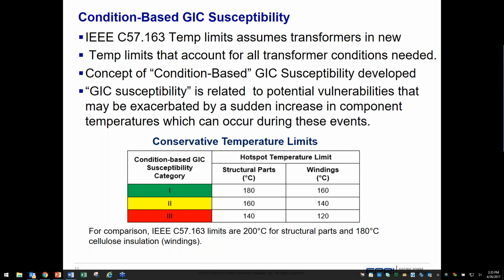We have a database of some 1,400 of the 37,000, so we do have actual statistics on a very good representative statistical sample of U.S. transformers, and we were able to put them in three different categories, green, yellow, and red, which are just what you would think they might be. Green transformers are in very good condition. We actually derated the IEEE standards by 10%, lowering the temperature to 180, meaning we would want to highlight it if it came within 10% of maximum temperature in this category.